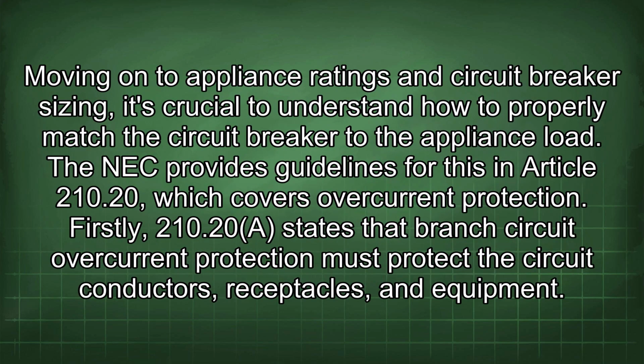Moving on to appliance ratings and circuit breaker sizing, it's crucial to understand how to properly match the circuit breaker to the appliance load. The NEC provides guidelines for this in Article 210.20, which covers overcurrent protection. Firstly, 210.20 states that branch circuit overcurrent protection must protect the circuit conductors, receptacles, and equipment.